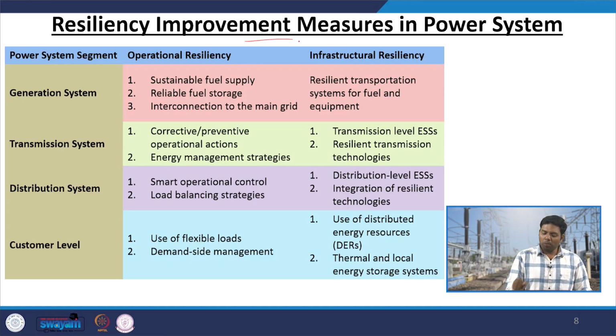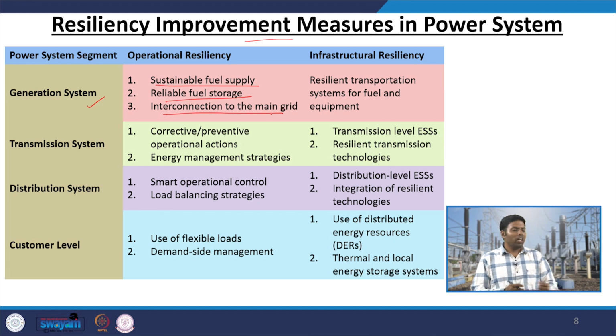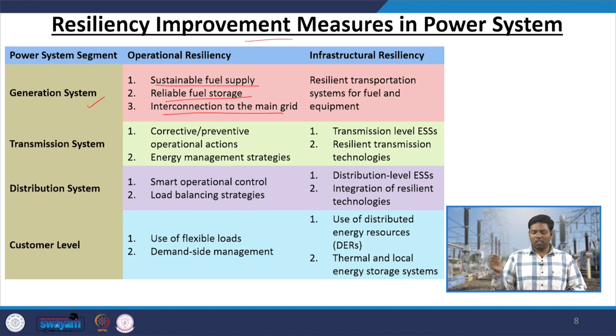So, resiliency improvement measures in the power system at different levels. In the generation system, at operational resiliency, you can ensure sustainable fuel supply, keep the fuel supply continuous, maintain reliable fuel storage as backup so you will not run out of it, or maintain interconnection to the main grid. That means you keep multiple connections with your main grid, so that if one connection gets disrupted, you still get supply from another substation. That is other than, it is a kind of transfer bus characteristic.